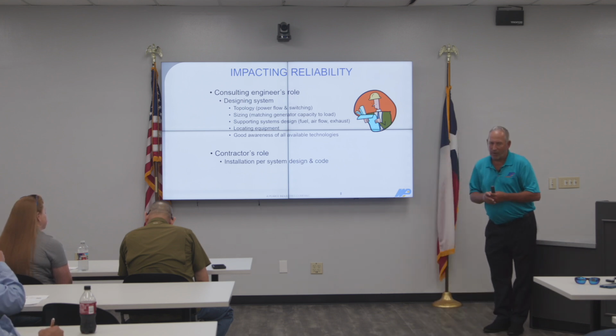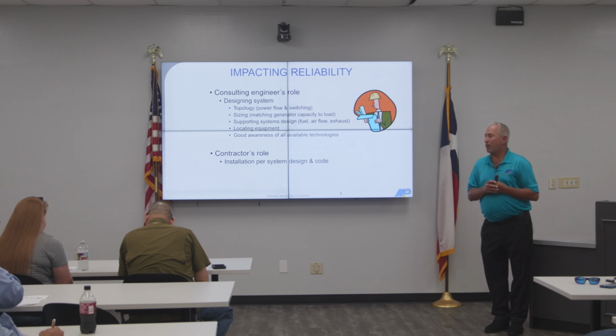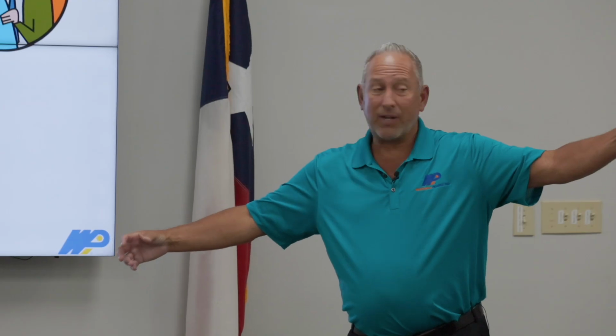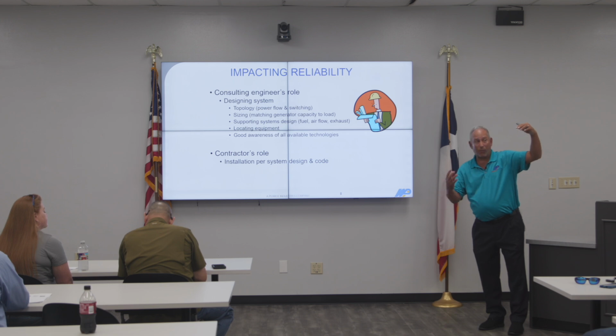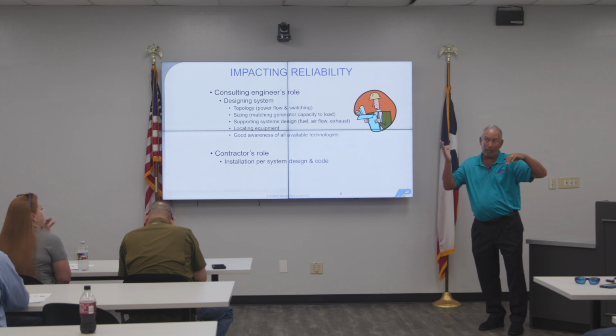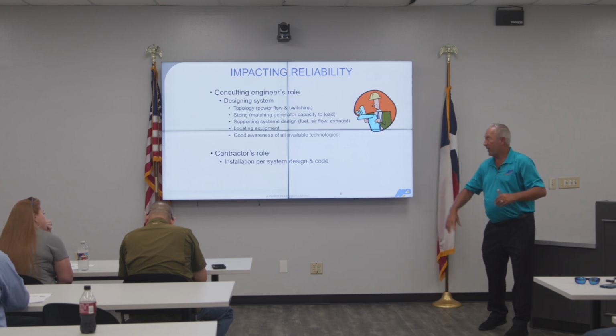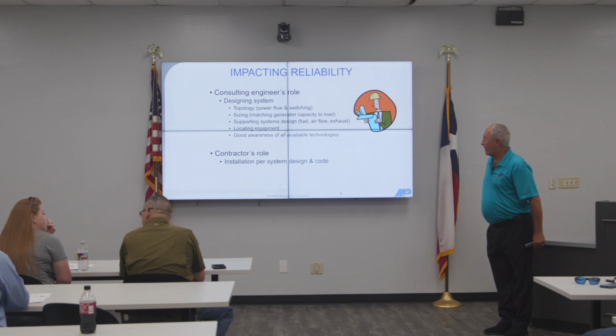The other thing you guys have are submersible pumps. The difference is that the windings are now long, you've seen those submersible motors, with long windings going down the motor casing. The problem is that because you've stretched the windings out, it's harder for us to make a good electromagnetic field around it. So submersible pumps are things we pause on, we want to know about it, and we want to know about the water column above it. Just to give you a little engineering behind why those are tricky for us.